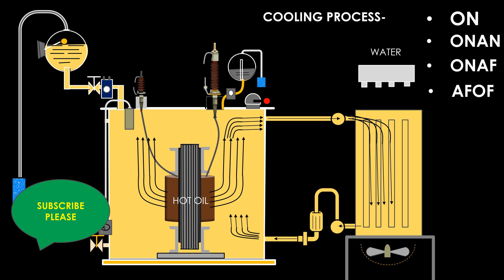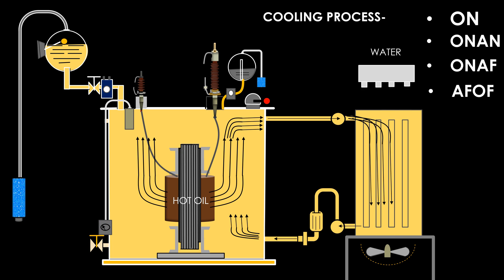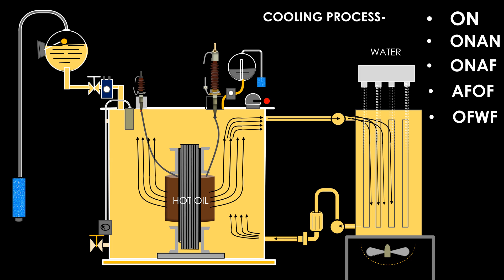Some large transformers are incorporated with a water cooling system, where cold water is spread over the radiator. This process is known as OFWF: oil force, water force. Generally, these types of cooling systems are employed to cool the transformer oil. Thank you for watching this video.